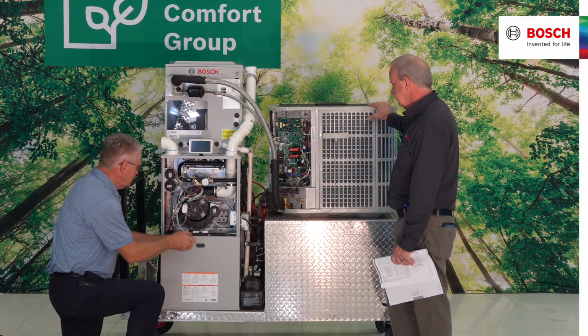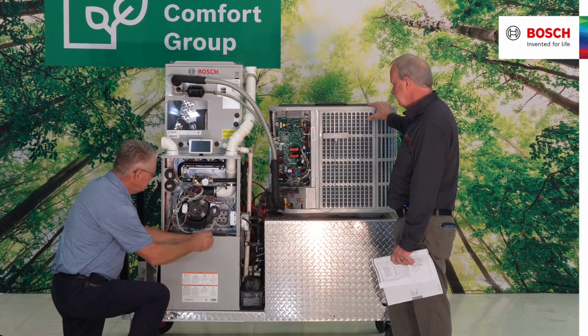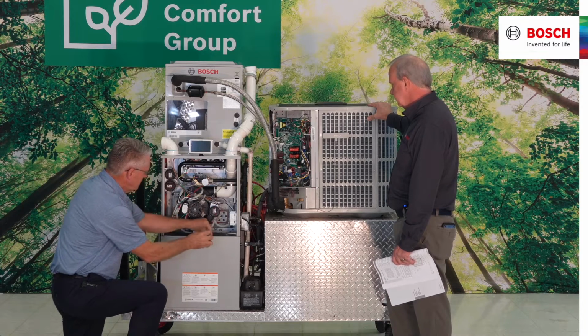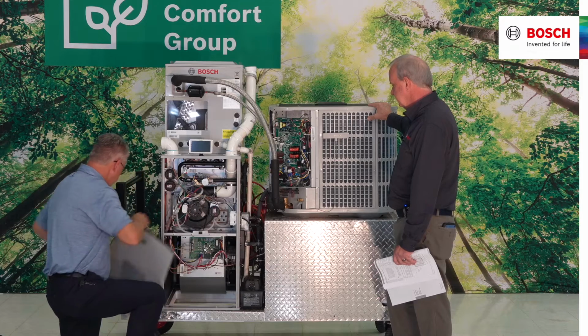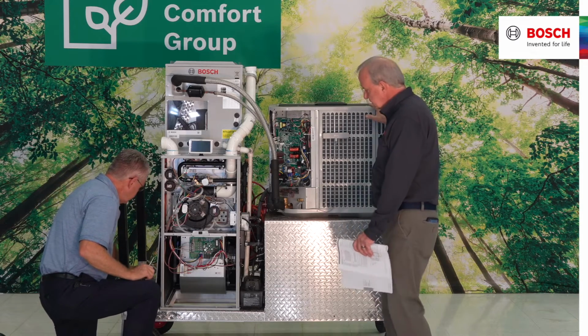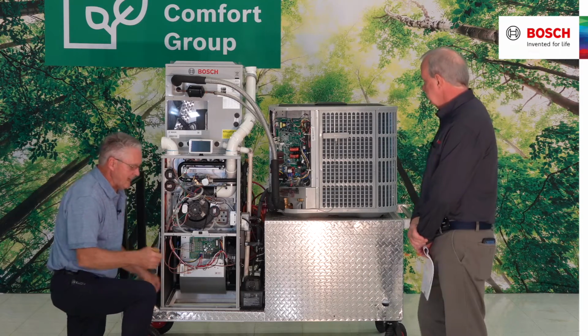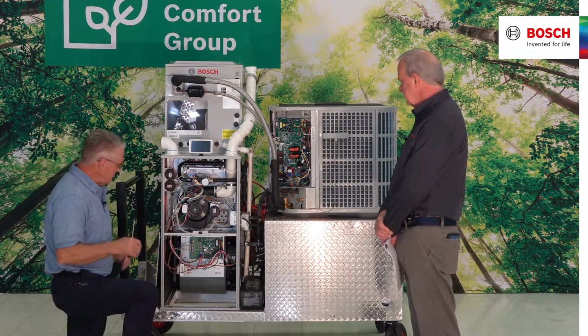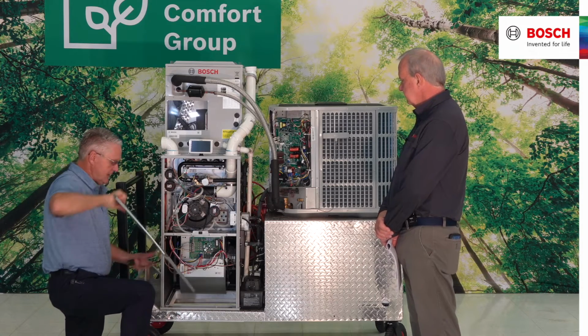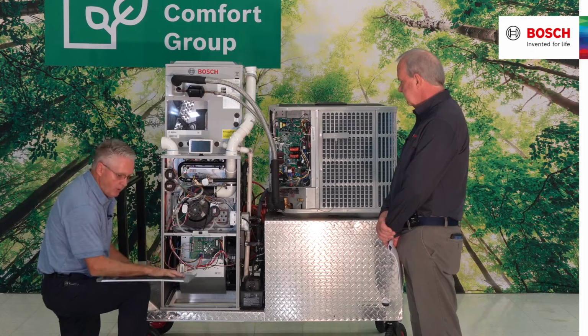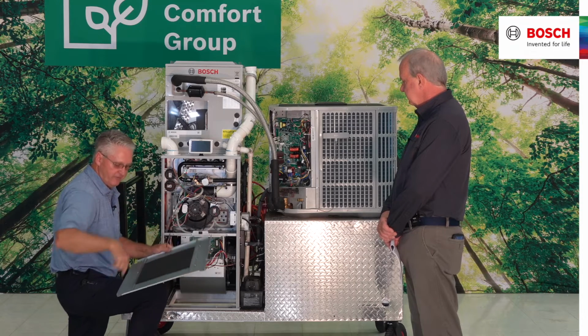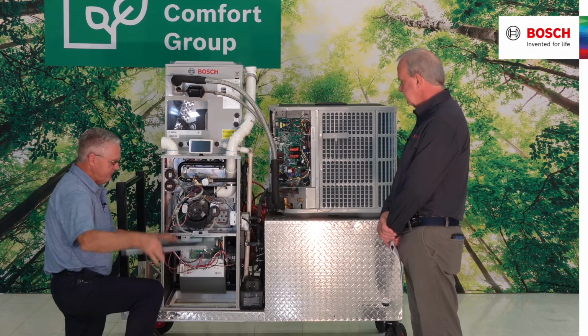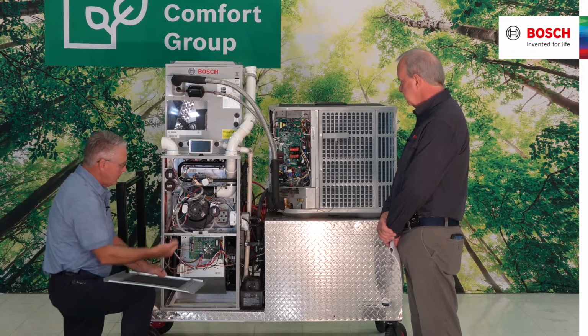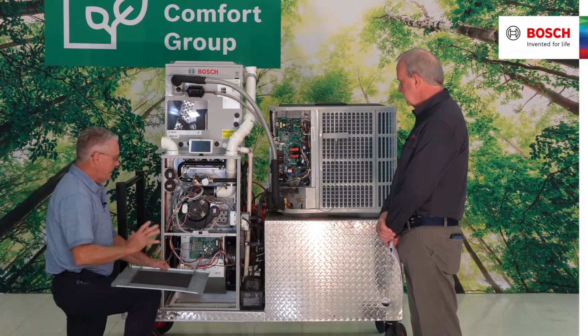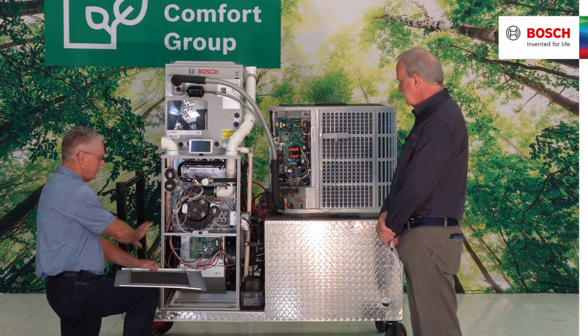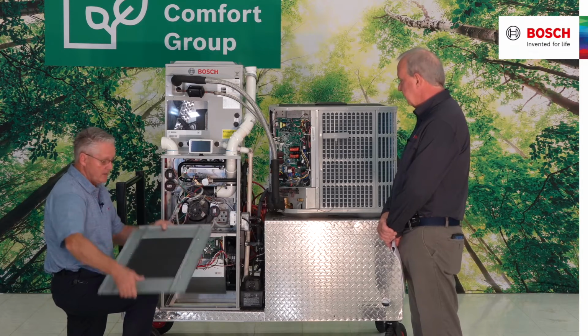So Ken, let's take this bottom panel off, and I'm going to remove the two screws that are closest to the door switch. Lift up, take off. One of the things we are going to notice when I take this furnace out of the box is that I am going to have a bottom plate located on the bottom part of the furnace that I'm going to have to take four screws out of before I'm able to use it in an upflow return air bottom situation. If I am using it in a side return situation, I can leave this plate on there. It is insulated.